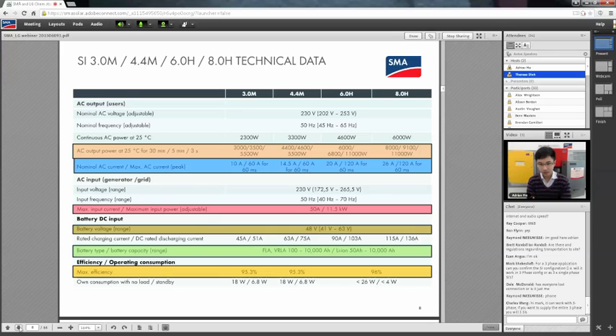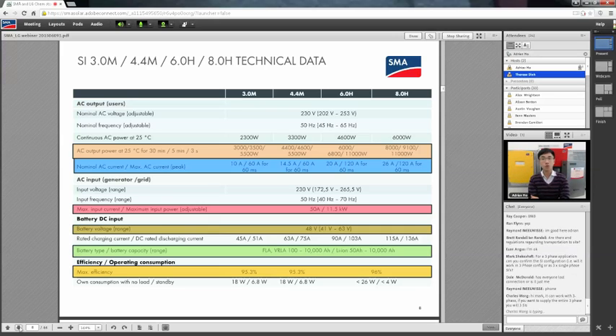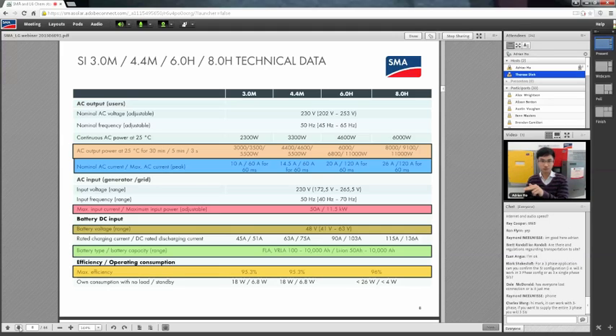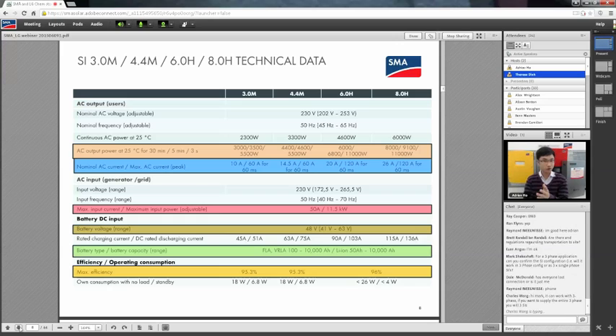The next one is the maximum current it can handle. For a short period of time, 60 milliseconds, the larger ones can take 120 amps. This ensures that not the whole system will trip, but only the circuit breaker of the circuit that has a fault will trip first. You don't want the whole off-grid system to shut down, you don't want your lights to go off, just those particular circuits that have a fault.